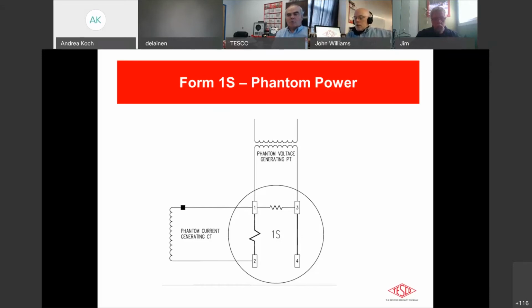Now there's talk about perhaps boosting that a little bit. The smart meters can actually take 240 volts across the volt coil. There's been talk also about some 480 units, but in essence, they're just a simple single voltage, single current element. So we see here in this diagram the application of what I was talking about before in terms of the phantom power application. In reality, in the real installation, you had the power going straight through the meter and consumed by the load on the downside of the meter.